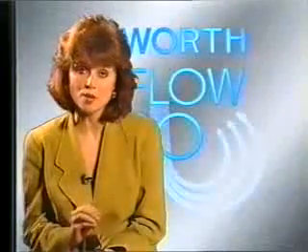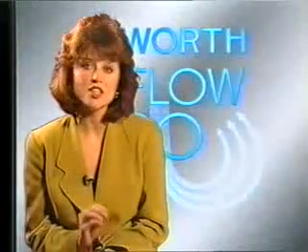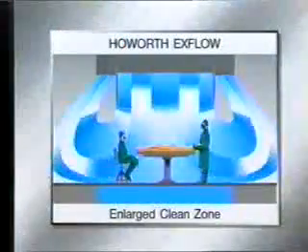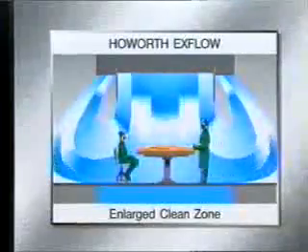Charnley and Howorth jointly developed the patented exponential flow system for operating theatres. Put simply, clean air enters the theatre from above, moving faster in the central area and slower towards the edge. The effect of this exponential profile of air is to form a trumpet-shaped flow which crosses the patient, moves towards the surgeon, and then back up to ceiling vents to be captured, filtered, and recirculated. Shown diagrammatically, the patient is free from potential infection by entrained contaminated air.